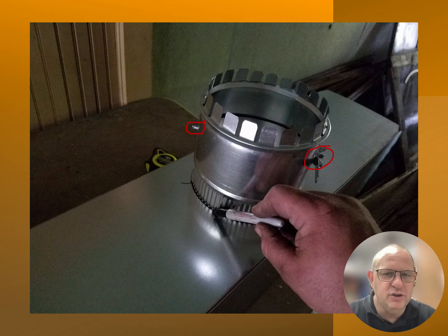Now, to get the takeoff onto the piece of metal or the trunk, what I'm going to do is flip it upside down so that the crimped edge is facing down. That's going to make sure I get a nice tight fit when I put this takeoff in there, so I don't have a very big air gap that I'm going to have to fill up with my mastic caulk that I'll be putting on later. So I'm drawing it out with a Sharpie, and I'm going to draw completely around that particular takeoff. If it was a square takeoff, I would measure it just like I'm doing right now, for the cutting of the square hole, a square to round takeoff. There are a lot of different takeoffs out there, but what we're going to do here is trace out the takeoff onto the main trunk, or the main plenum that's coming off of the furnace or the air handler, and then we are going to cut into that pipe itself.